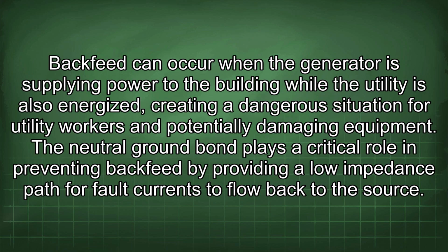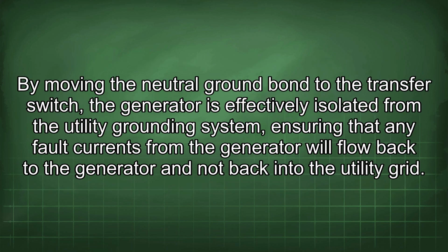Backfeed can occur when the generator is supplying power to the building while the utility is also energized, creating a dangerous situation for utility workers and potentially damaging equipment. The neutral ground bond plays a critical role in preventing backfeed by providing a low impedance path for fault currents to flow back to the source.